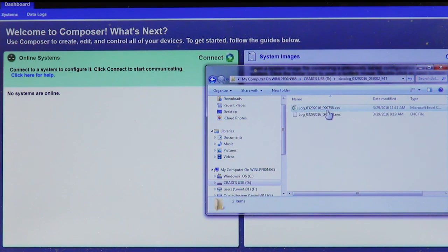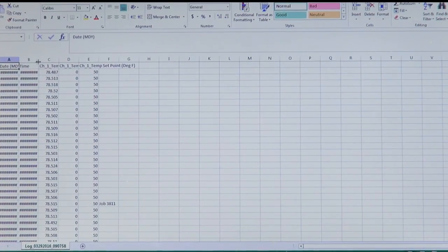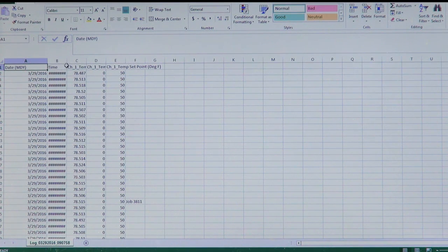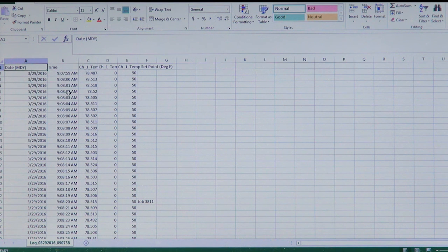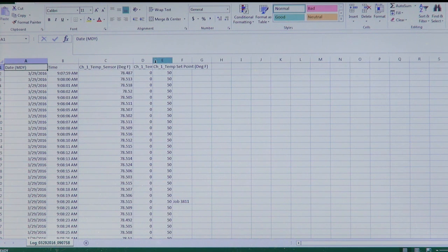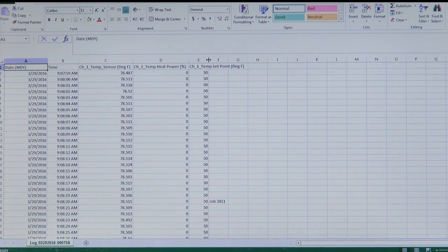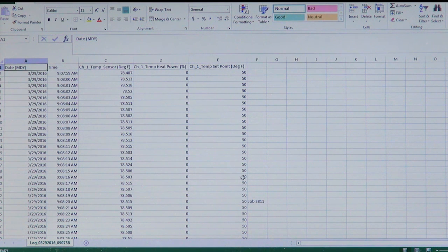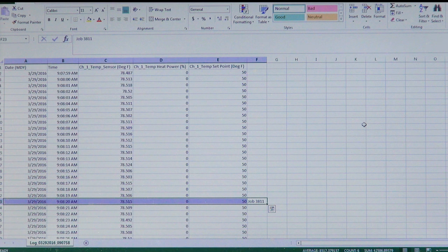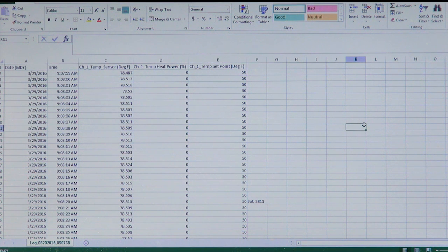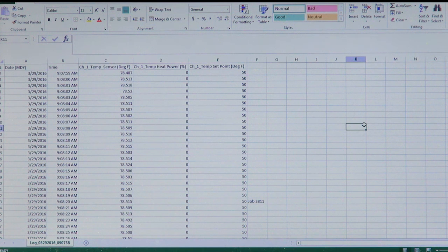Going back into the thumb drive, you can now see a .CSV version of the file. Looking at the data logging record: the first column is date, second column is time. Notice I was logging in one-second increments. There are the temp sensor values, the percent heat power values, and the set point values. An annotation note — 'job 3811' — is date and time stamped in the record. For automatic and manual data log file transfers, we've created another video — check that out, along with other F4T resources at www.watlow.com/f4t.